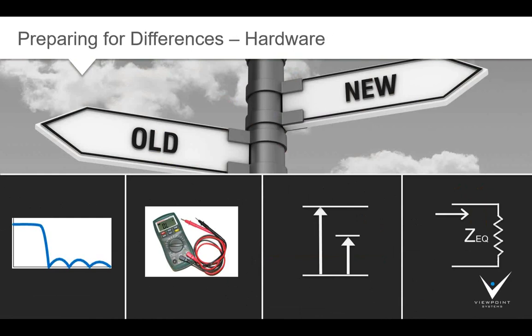And the last one, which was another head scratcher, was the battery manufacturer. These people wanted to measure the AC impedance of a battery by driving a small AC ripple on top of the battery DC voltage. We found that the impedance measurements were consistently different between the old and new testers. Turned out that the old system drove a different current level into the UUT and also had an analog input impedance about 1,000 times less than the new system. And apparently the battery had some nonlinear behavior which caused the differences in the testers. A significant amount of time was spent understanding the differences between the old and new before agreeing that the new test system was doing its job properly, albeit differently.